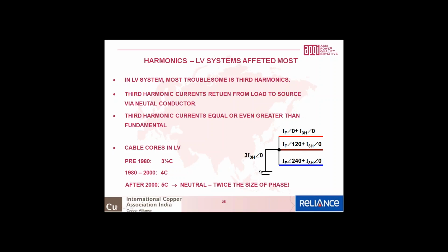Therefore, on the neutral, the fundamental components, one at angle 0, one at angle 120 and one at angle 240, add up to zero, whereas the third harmonic component adds up to 3 times. That is the reason why, when the third harmonic component is high, the neutral current is high, and whenever there is a neutral burnout, you can suspect a huge amount of neutral current flow. That is also why, when specifying cables before the 1980s, we used a 3.5 core cable, where the neutral was half the size of the phase.